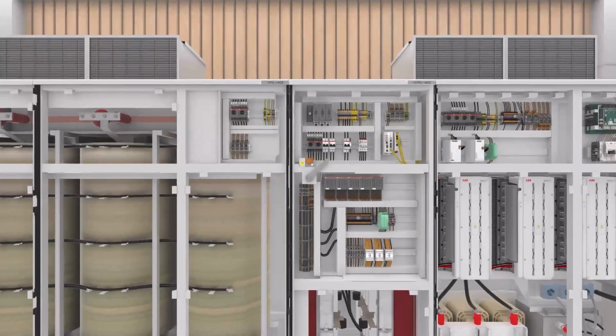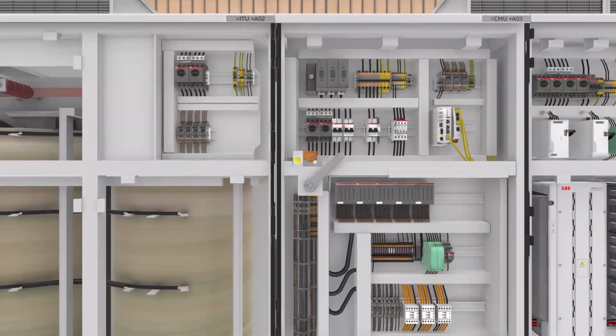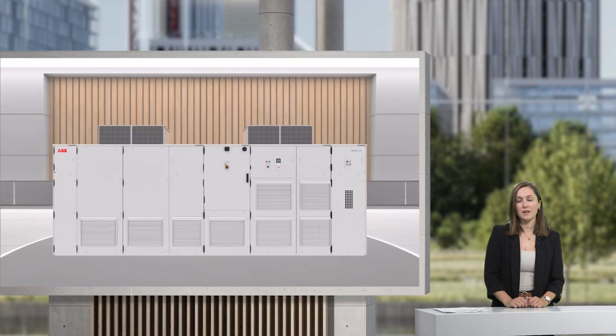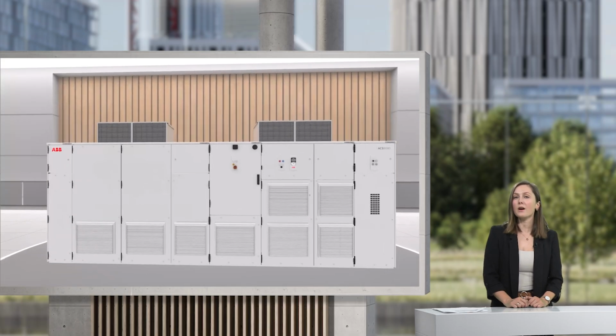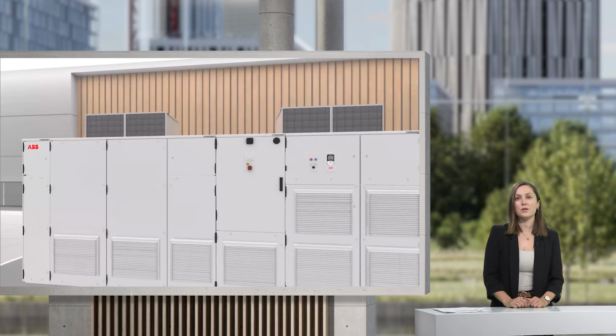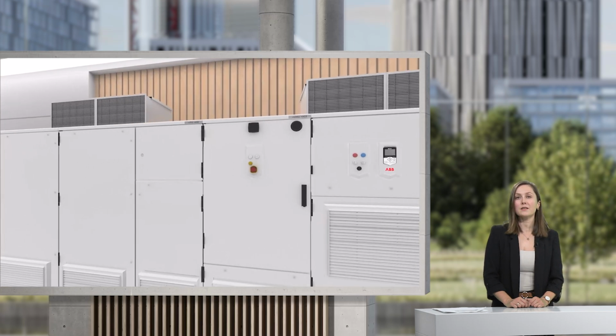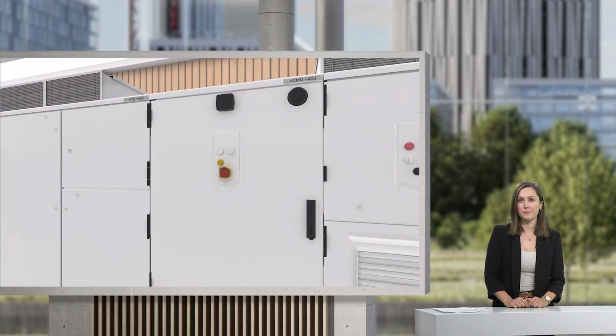Our commitment to safety is comprehensive. The integrated DC grounding switch ensures there is no accidental contact with any energized components during maintenance, offering an additional layer of safety. The fuseless design offers more accurate protection than traditional fuses by reducing the risk of failure during operation.